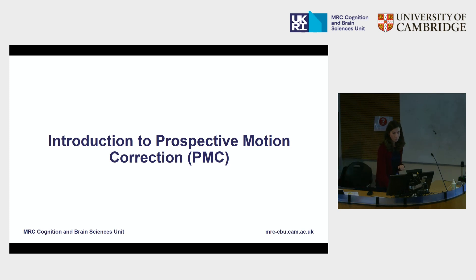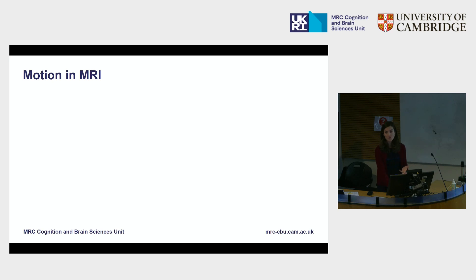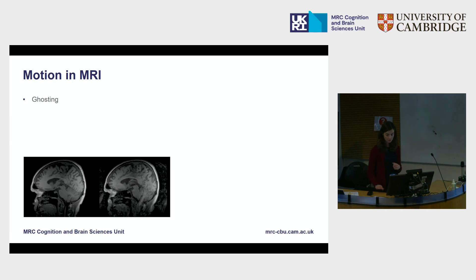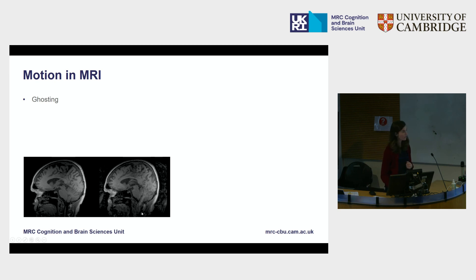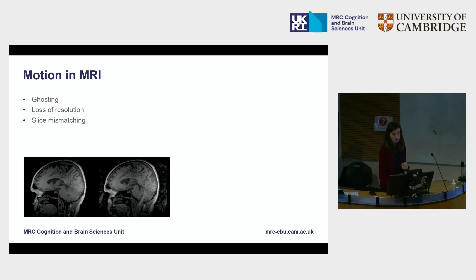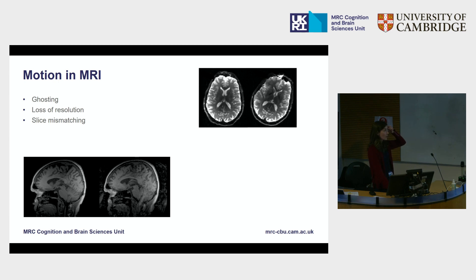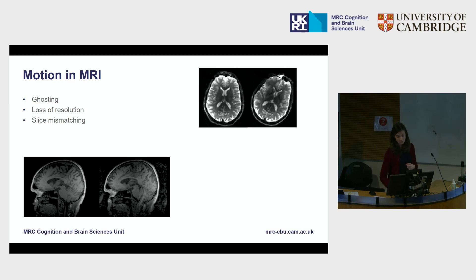So, prospective motion correction or PMC. Most of you in the room, if you do work with MRI, will be aware that there are lots of consequences of head movement. We might see some ghosting — there are examples here, such as a double of the image appearing at the back of the brain, and striping across the brain. Another very common impact is the loss of resolution, so images come out blurry or smoothed out. We can also have slice mismatching, which is particularly problematic for fMRI or diffusion MRI, where slices may be completely mismatched, meaning voxels no longer line up and some form of correction is needed.